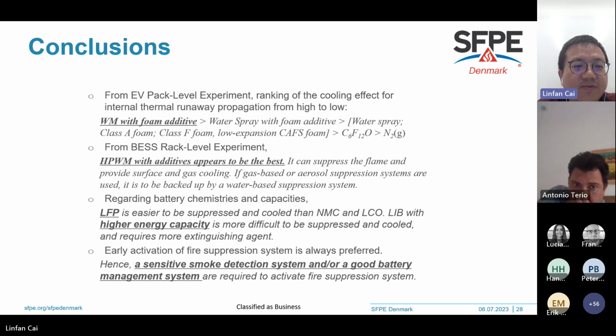So in the rack level experiment, high pressure water mist with additive appears to be the best, because it can both suppress the flame and also provide surface and gas cooling. So if gas-based or aerosol suppression systems are used, it is suggested that they be backed up by a water-based suppression system.